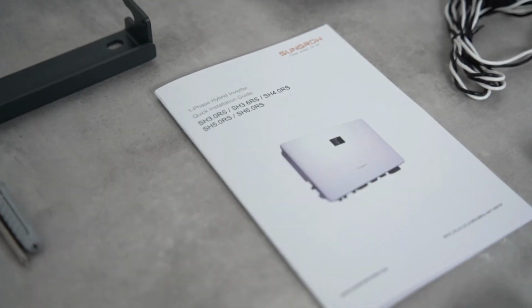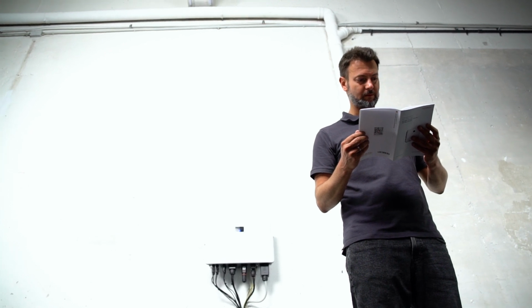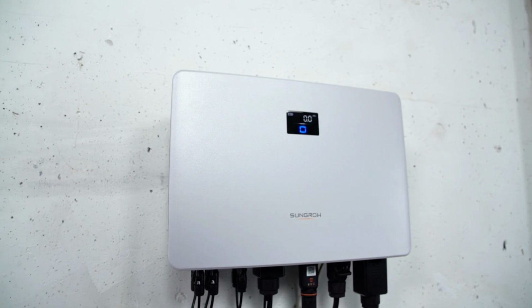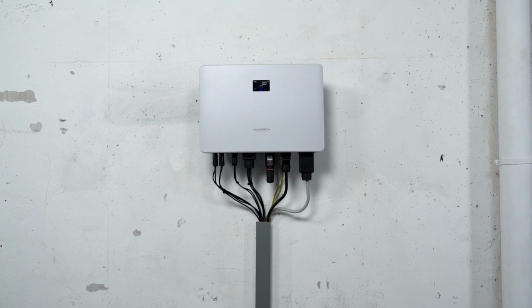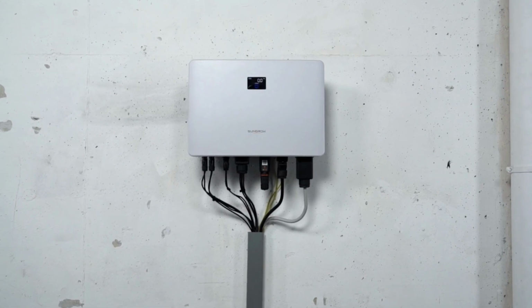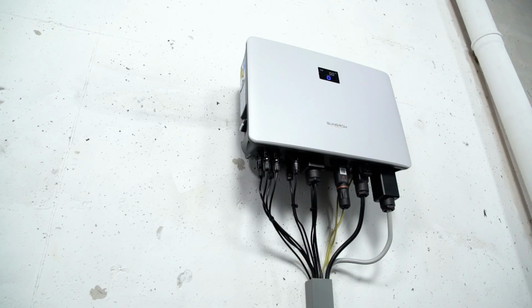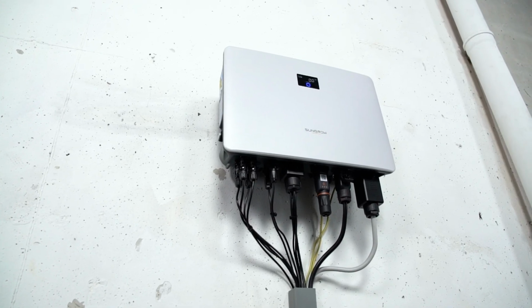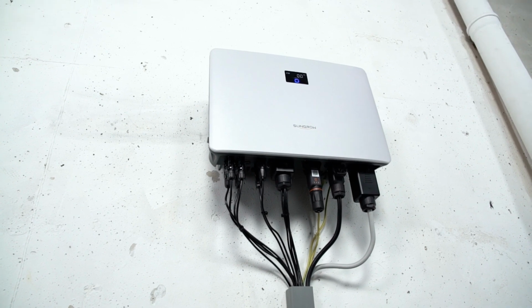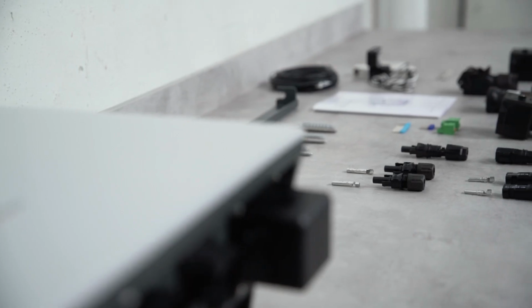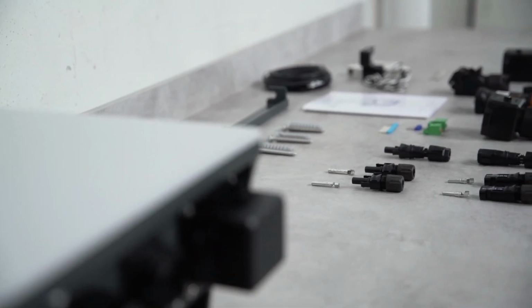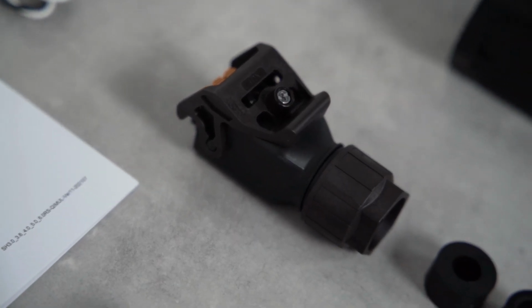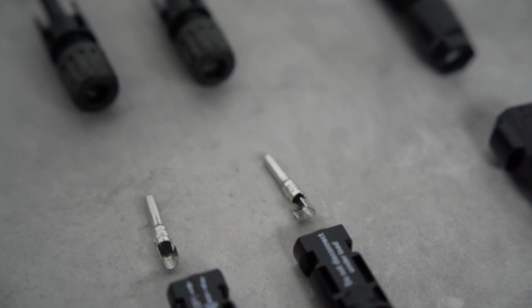Before starting the installation, please read the safety instructions in our manual. You need a suitable place for the inverter. This means it should be a room where no flammable materials or gases are stored. The wall must be fireproof and able to bear the weight of 40 kg. All screws and plugs required for the installation are already included in the delivery. You only need your own tools and cables.